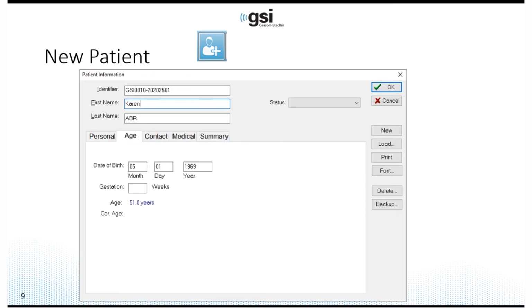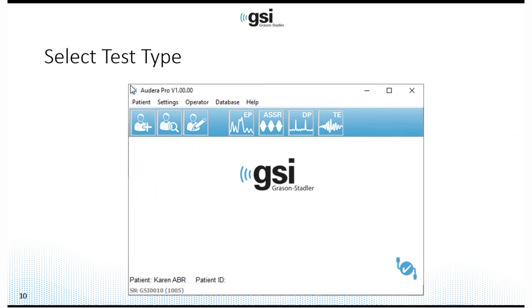But for ABR, if you're going to use the normative data provided, then you will have to go to the age tab and enter a birth date. So the infant norms will not appear if you're testing an adult or vice versa. If you leave this blank and you launch the latency intensity function, it will also be blank. So if that happens during collection, you just have to remember to enter the date of birth. Once you've entered the patient name, you're ready to select the test type and get started.